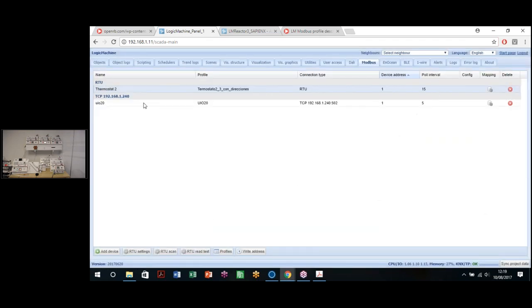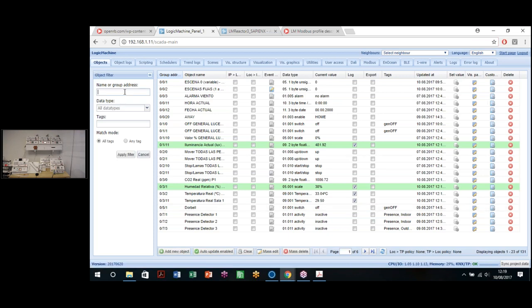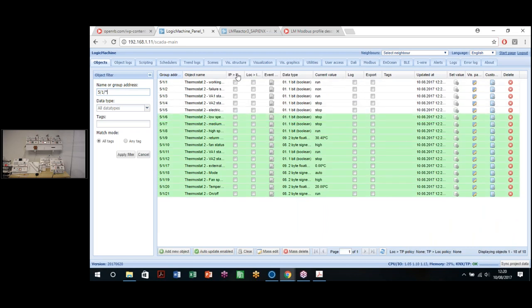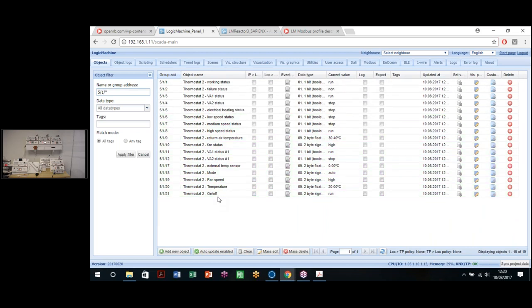after 15 seconds, it will receive all the information from this RTU device. When we go to the objects tab and filter, in this case by 511, I'm sorry, we can see here that we have all the new objects created, and here we have the values of the Modbus. If we change any value directly from the Modbus device, for example, the fan speed or the set point, we will see it in temperature, the set point will change, in this case, we've seen 18 degrees. And this information can also be changed from here.